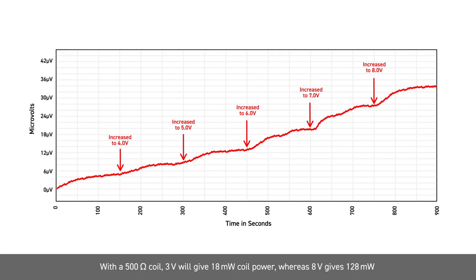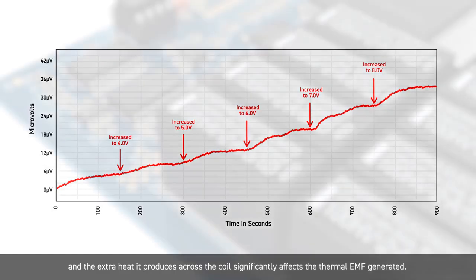With a 500 ohm coil, 3 volts will give 18 milliwatts of coil power, whereas 8 volts gives 128 milliwatts. The extra heat produced across the coil significantly affects the thermal EMF generated.